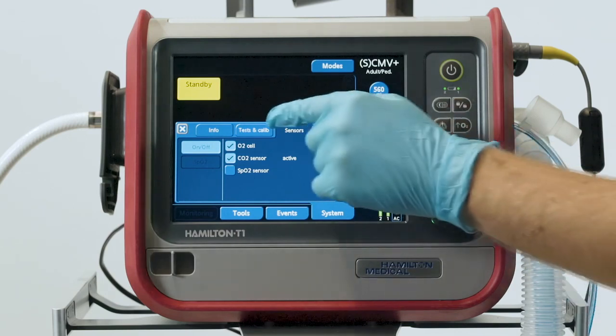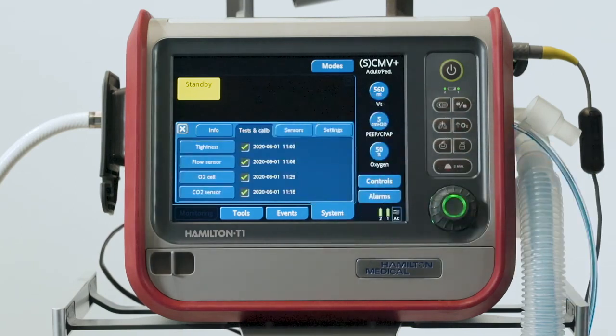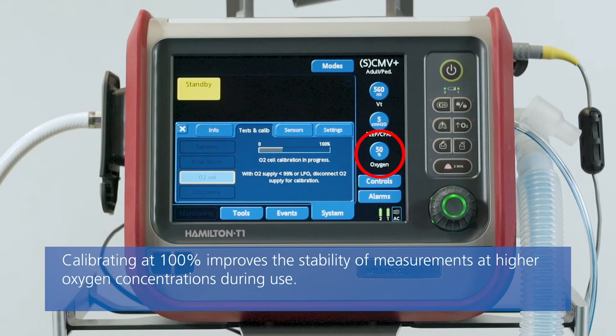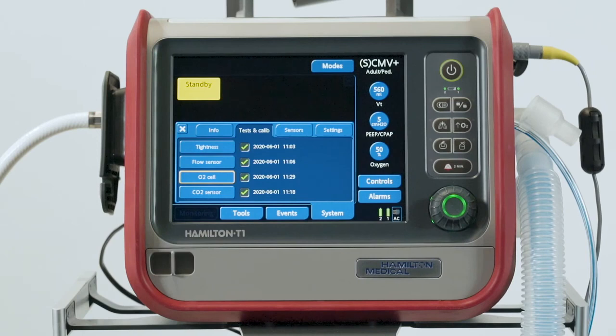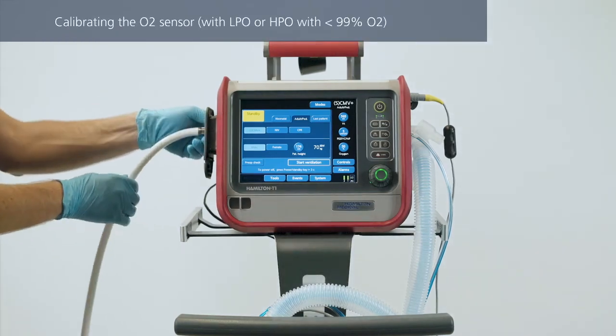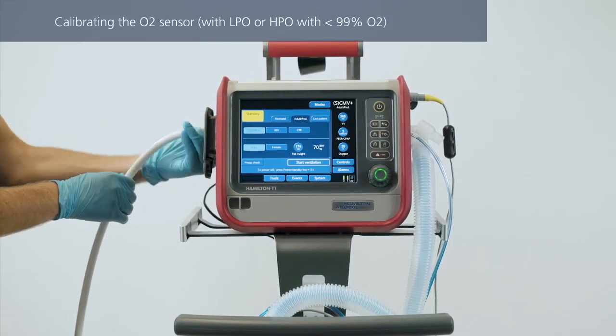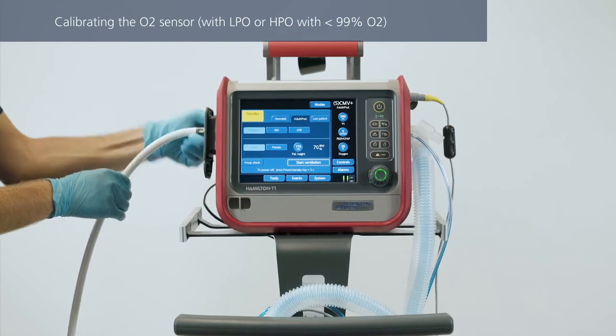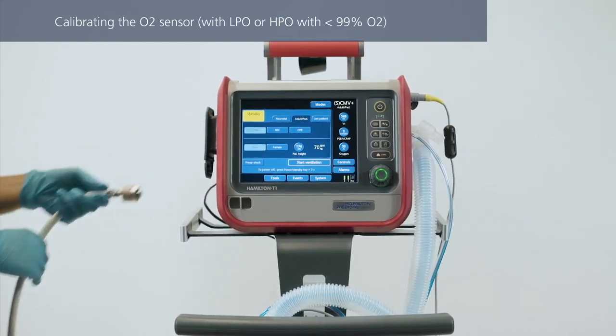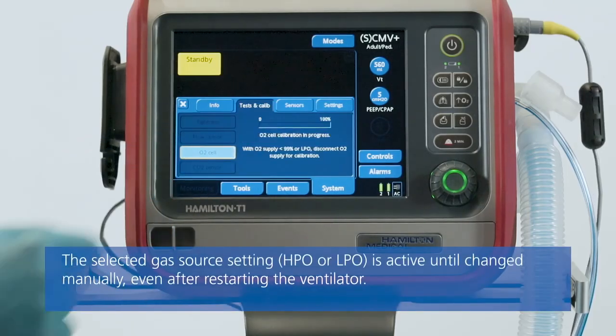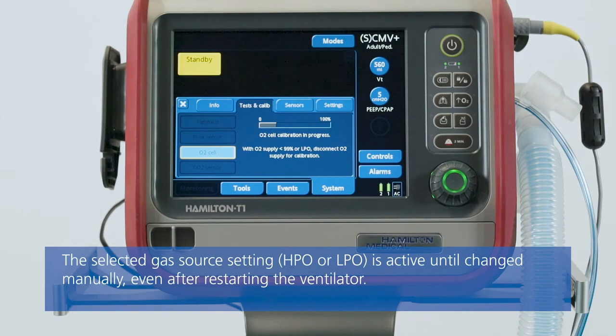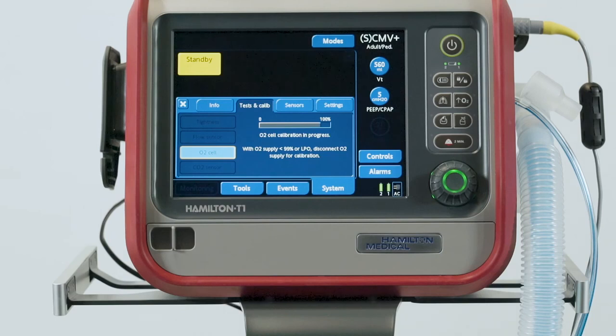To calibrate the sensor with 100% oxygen, set the oxygen control to 22% or higher. The high-pressure gas source needs to be connected. When calibration is complete, you should see a green check mark in the O2 sensor checkbox. If you're using low-pressure oxygen, or high-pressure oxygen with less than 99% oxygen, disconnect all oxygen supplies before you start calibration. If the oxygen supply is disconnected, calibration will be performed with 21% oxygen, regardless of the current oxygen setting.